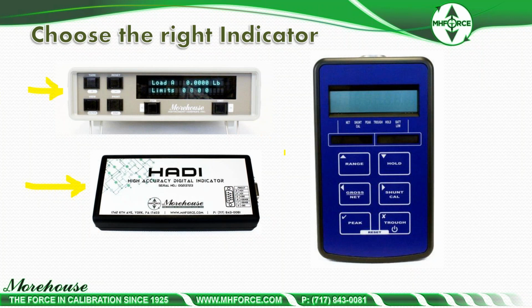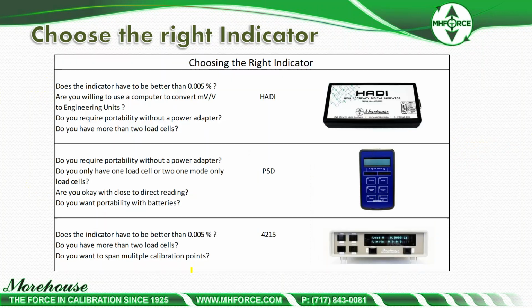The disadvantage is it requires a computer. As you see, there is no readout here. And then we have this one that's a little handheld 2-channel one on batteries. It works well if you're doing a verification check. Really not the greatest for calibration, but really good if you had a press or you just wanted to put a load cell in something and see what the force was as far as a check standard. So you just kind of have to go through.